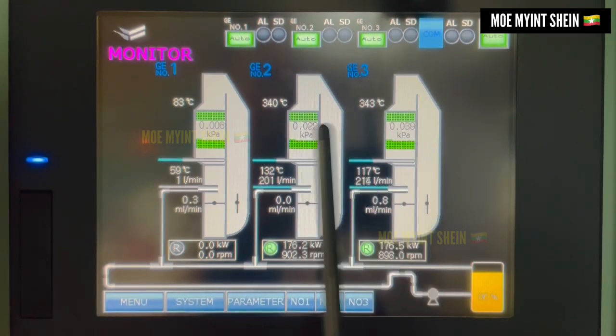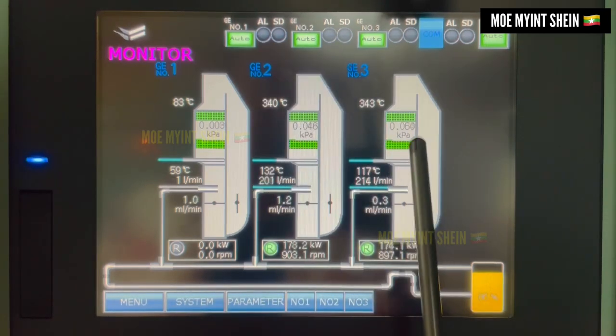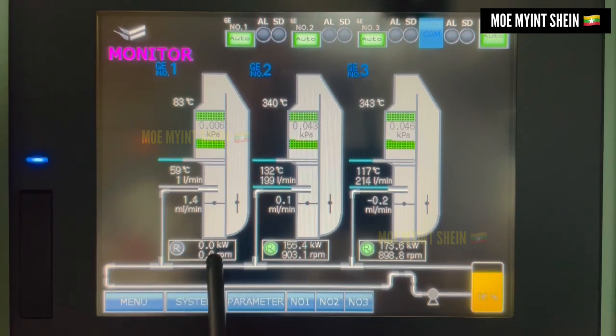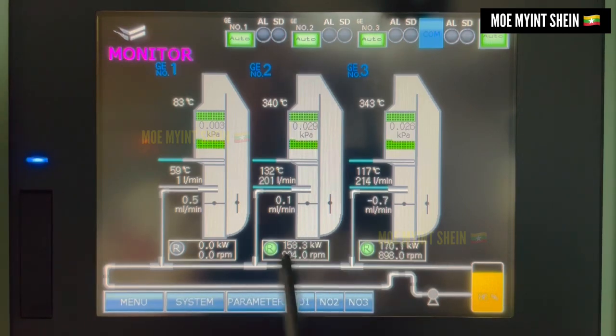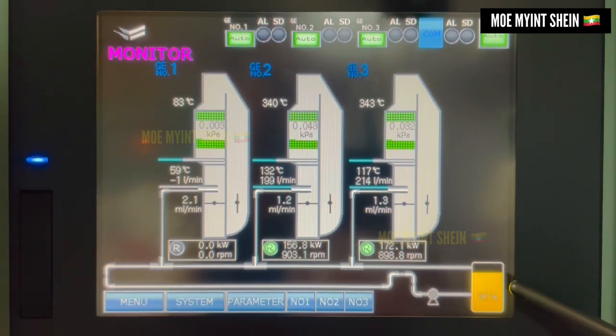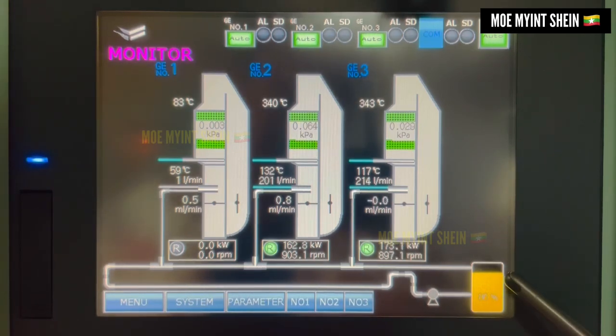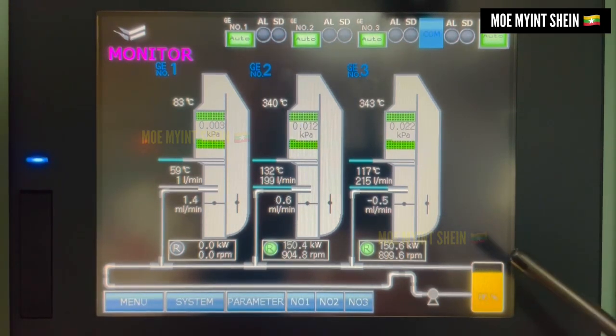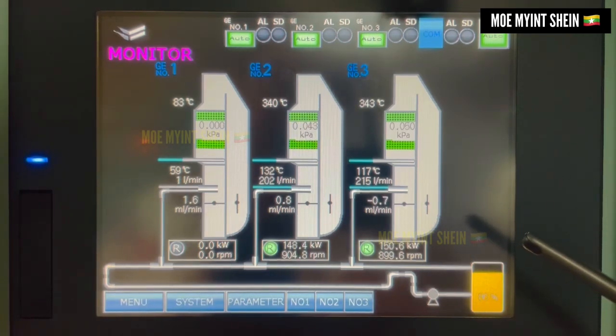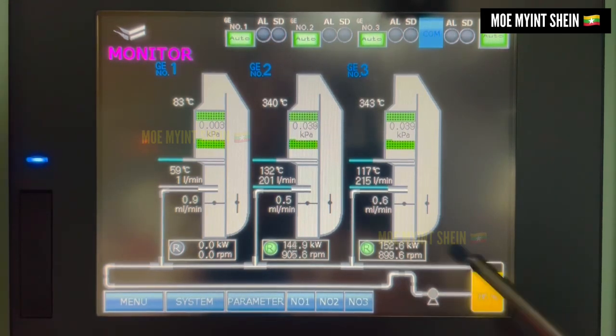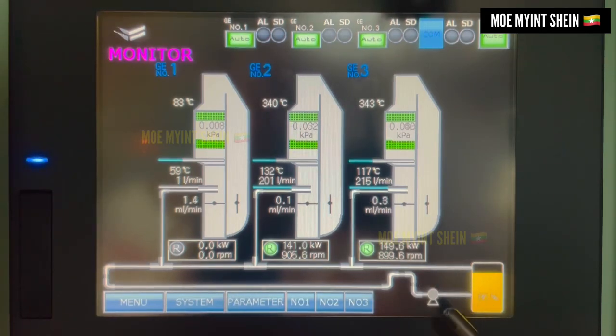At present, number two and number three generator engines are running. Number one is stopped — that's why its RPM and kW shows zero. A running generator shows kW and RPM on the panel. Urea tank level shows 86% of its full capacity. A temperature sensor is fitted at the urea tank. High temperature alarm activates at 40°C and the system will shut down at 45°C. If the vessel trades in hot zones, additional cooling arrangements are required. If the vessel trades in cold regions, no additional cooler is required.